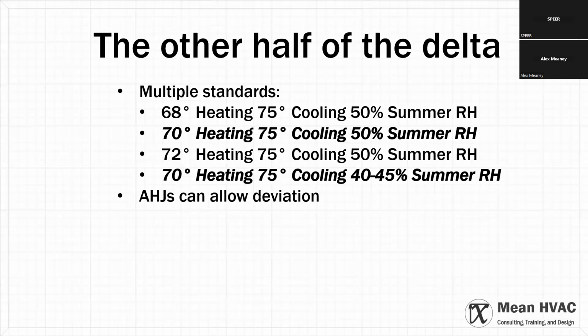You might want to change your operating relative humidity to something in the 40 to 45 percent range, wherever that standard is, where you start to get a small latent load, a small dehumidification load, because that's going to be the number where, when you let outside air in, it's drying out your house, not making it more humid until it gets to that point, right? When you find that, that should probably drive your assumptions about equipment performance. Equipment doesn't perform as well with dry air as it does with wet air.